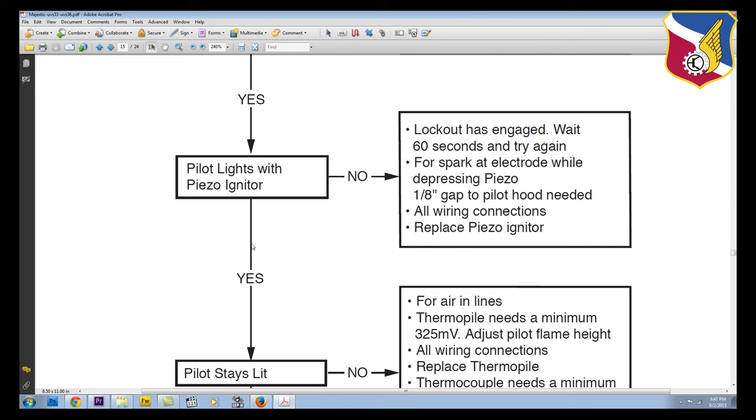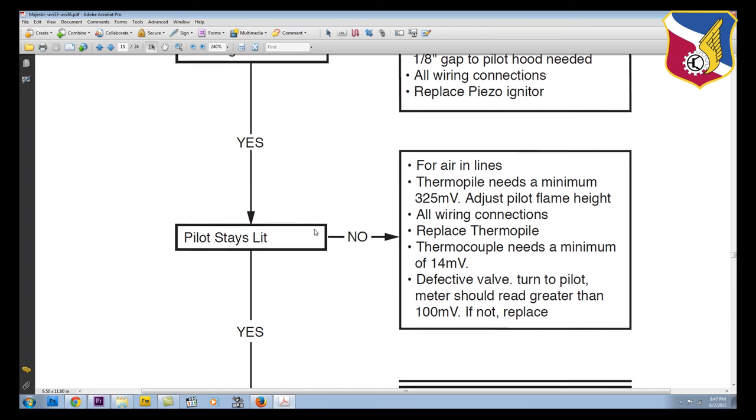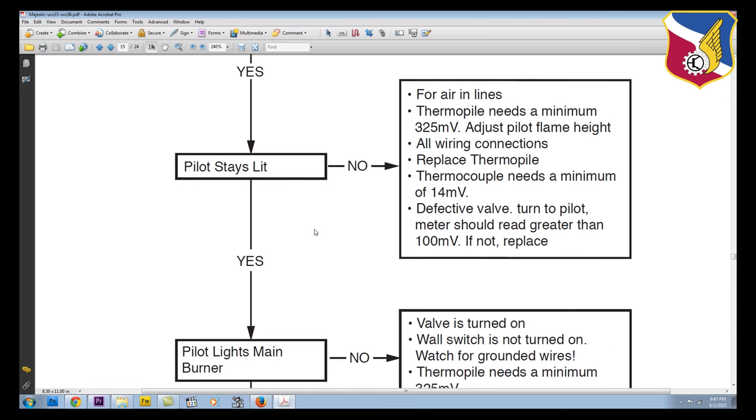Now if you do have gas coming into it, does the igniter come on? Now if it doesn't come on then maybe it's in lockout has engaged, and so wait 60 seconds. After you wait 60 seconds, if it doesn't come on then check these specs right here. Does it have one-eighth inch of a gap to the pilot hood? Do you have wires connected? And if everything checks out correctly then maybe you have a bad igniter, so replace that.